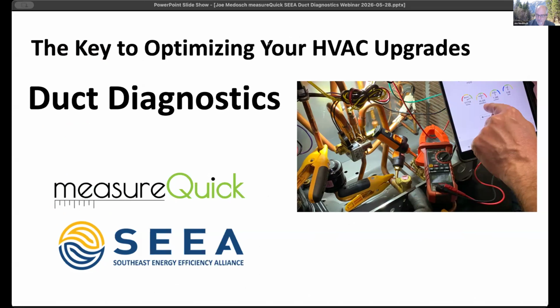And when you have a lot of supply duct leakage, the house is going negative. And if you've got a domestic hot water tank in the house still, that's actually natural drafting, you can actually backdraft that appliance and actually cause carbon monoxide issues and other combustion issues in the house because of duct leakage. So these are some of the things that you were doing and not realize that if you seal up the return, maybe now my supply is still leaky. So these are all things you need to be doing.